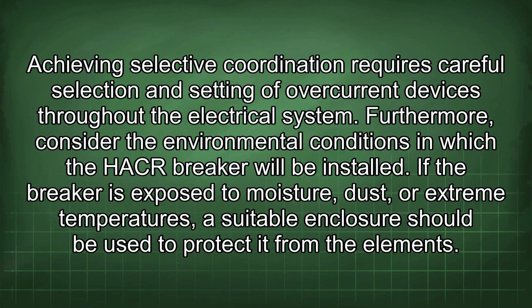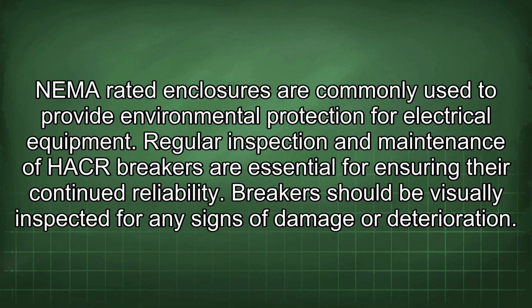Furthermore, consider the environmental conditions in which the HACR breaker will be installed. If the breaker is exposed to moisture, dust, or extreme temperatures, a suitable enclosure should be used to protect it from the elements. NEMA-rated enclosures are commonly used to provide environmental protection for electrical equipment.